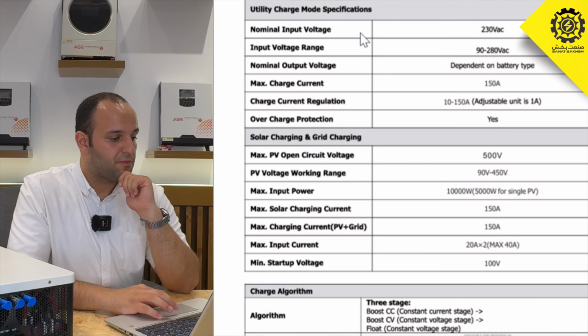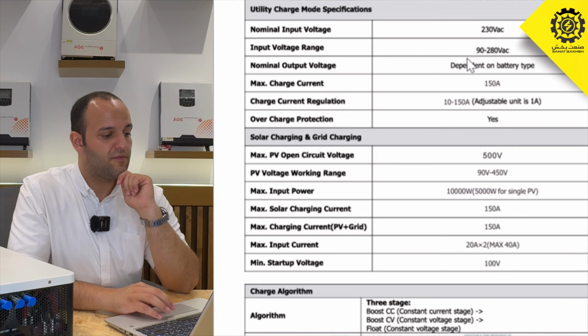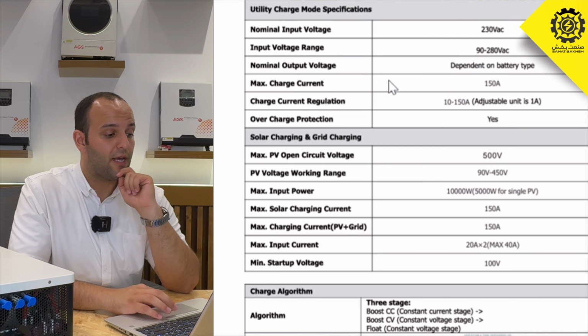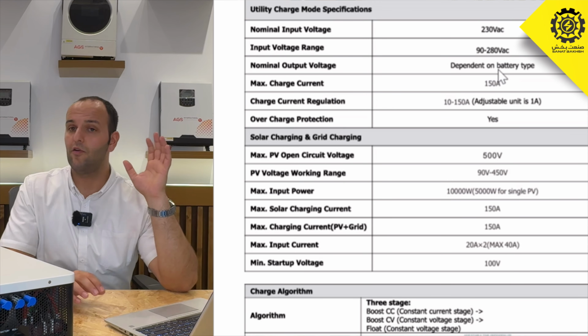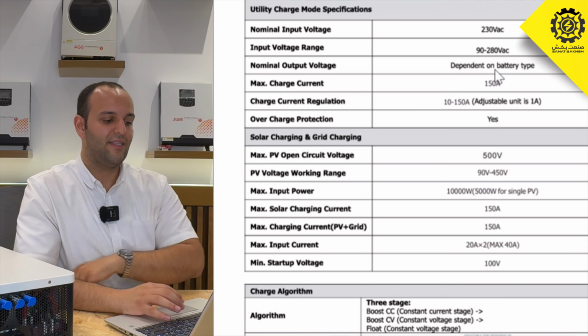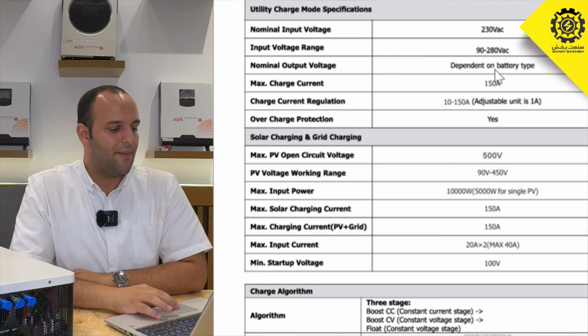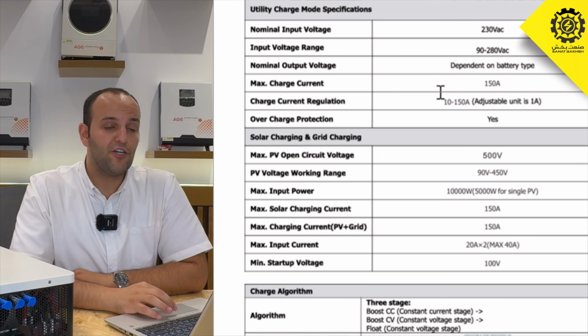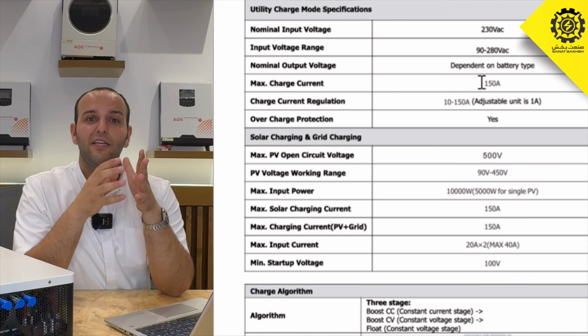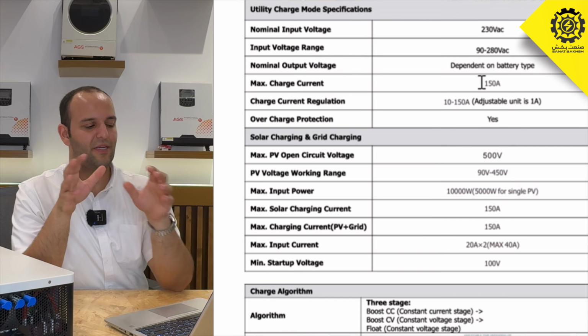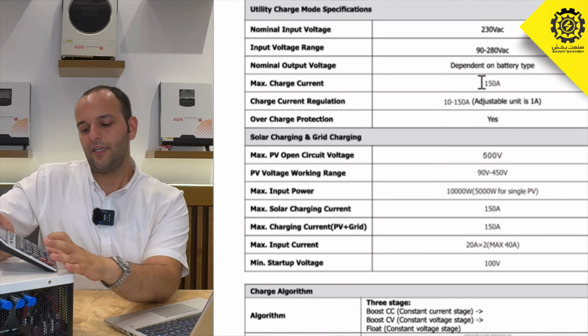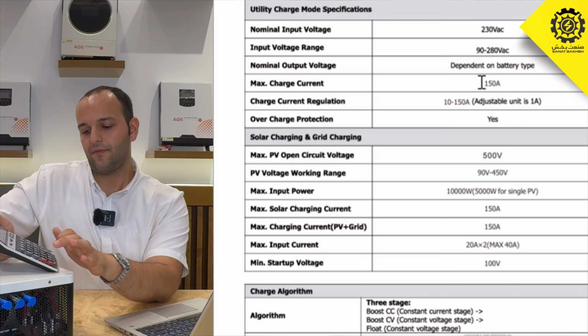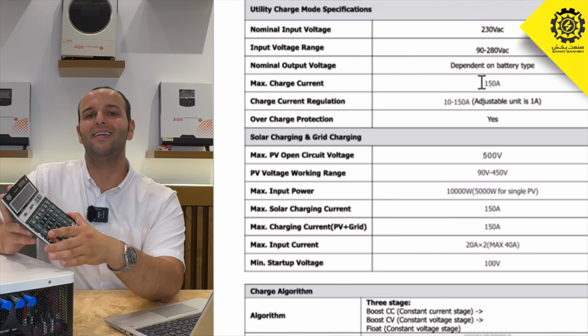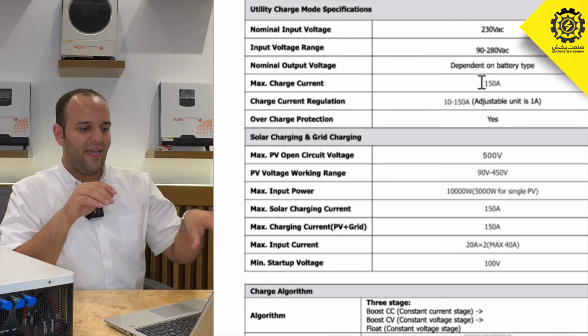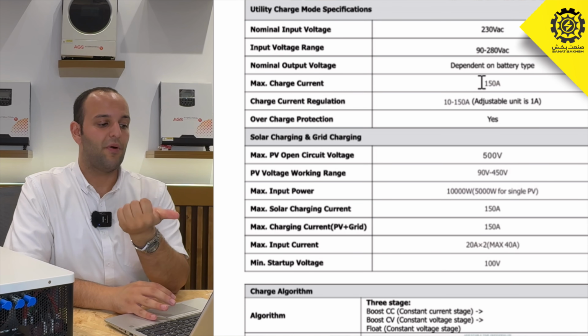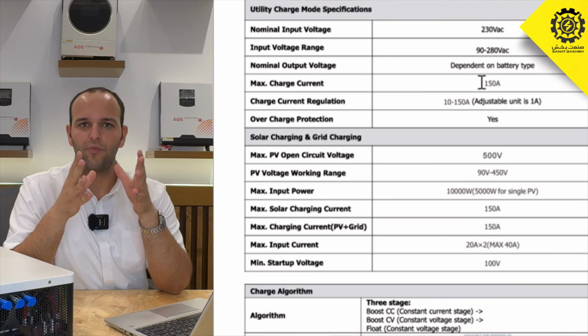Utility charge mode specification. Input voltage range is 90 volts to 280 volts. Nominal output voltage depends on battery type. The output voltage depends on the battery type, lithium, AGM or gel battery. Max charge current: the charge current is 150 ampere. Imagine you have a 15 kilowatt battery. A 15 kilowatt battery at 52 volts in lithium means you have exactly 288 ampere-hour battery. If this inverter can charge the battery with 150 ampere current, it means you can charge your battery in less than 2 hours.